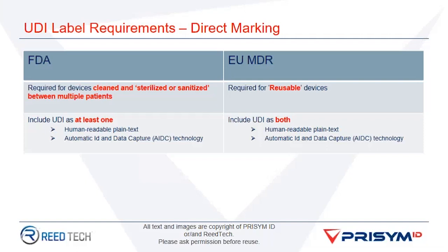Okay, and I've seen a couple of questions on this topic having to do with different levels of labeling, primary and secondary. Are there considerations with respect to what must appear at different levels of labeling? Yeah, that's a good question. You can do some additional research in the GS1 general spec. There are requirements for the different packaging levels to have a unique device identifier. Some of the information of the production identifiers flows to those higher levels.